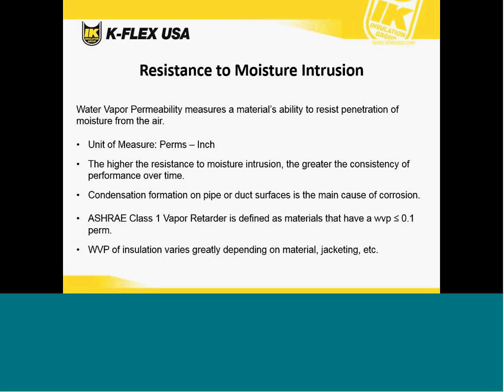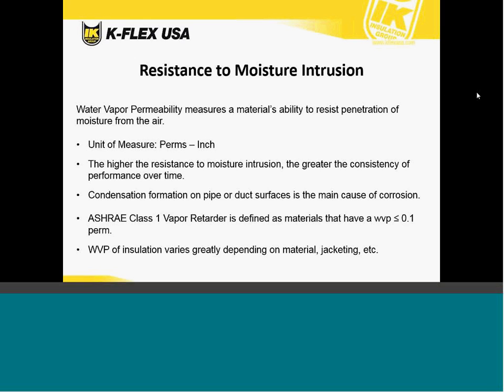Condensation formation on pipe or duct surfaces is also the main cause of corrosion, another thing that we're trying to avoid with a proper insulation system. It's important to know that an ASHRAE Class 1 vapor retarder is defined as a material having a water vapor permeability less than or equal to 0.1 perm. Vapor permeability of insulation varies greatly depending on the material.